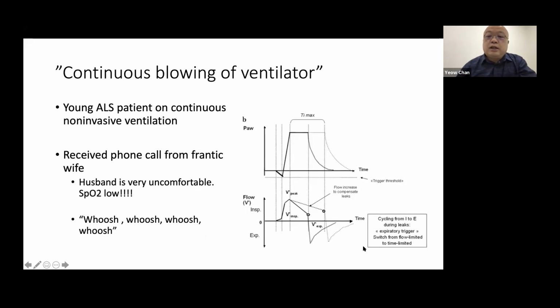So this is illustrated in this picture, which is shown. This article is from BMJ Thorax. I'm sorry, I don't have the reference here, but you can contact me. I can send you the original article, or I will send it to Shu Xian. So this is a flow time curve. You remember from the ventilator lectures that for flow cycle modes, the machine will push to a certain pressure, but when does it cycle off? It cycles off when the flow drops to a fraction of the initial flow.